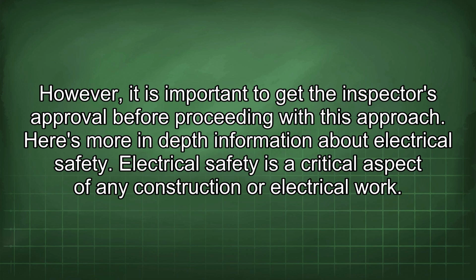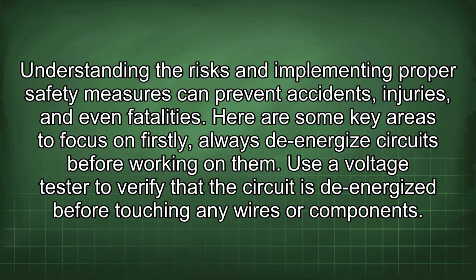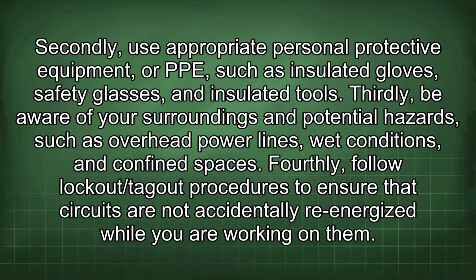Here's more in-depth information about electrical safety. Electrical safety is a critical aspect of any construction or electrical work. Understanding the risks and implementing proper safety measures can prevent accidents, injuries, and even fatalities. Here are some key areas to focus on. Firstly, always de-energize circuits before working on them. Use a voltage tester to verify that the circuit is de-energized before touching any wires or components. Secondly, use appropriate personal protective equipment or PPE, such as insulated gloves, safety glasses, and insulated tools. Thirdly, be aware of your surroundings and potential hazards, such as overhead power lines, wet conditions, and confined spaces. Fourthly, follow lockout/tagout procedures to ensure that circuits are not accidentally re-energized while you are working on them.